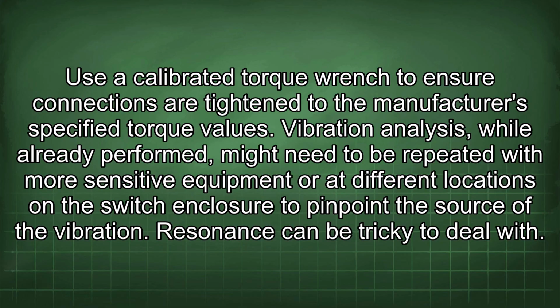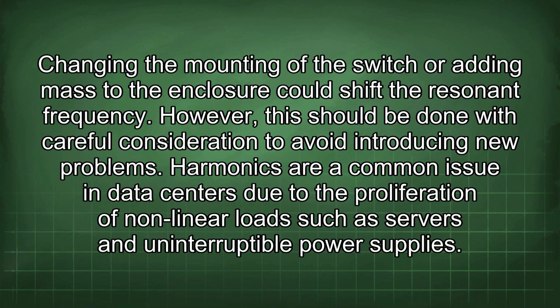Vibration analysis, while already performed, might need to be repeated with more sensitive equipment or at different locations on the switch enclosure to pinpoint the source of the vibration. Resonance can be tricky to deal with. Changing the mounting of the switch or adding mass to the enclosure could shift the resonant frequency. However, this should be done with careful consideration to avoid introducing new problems.